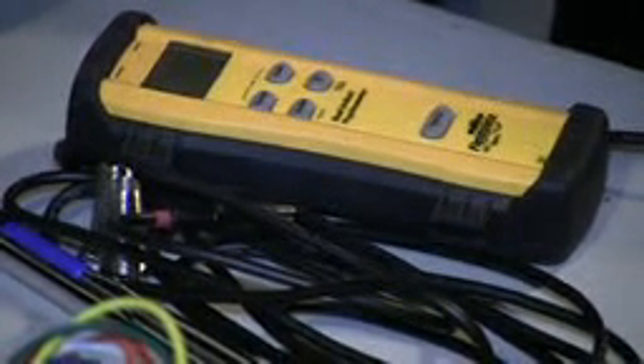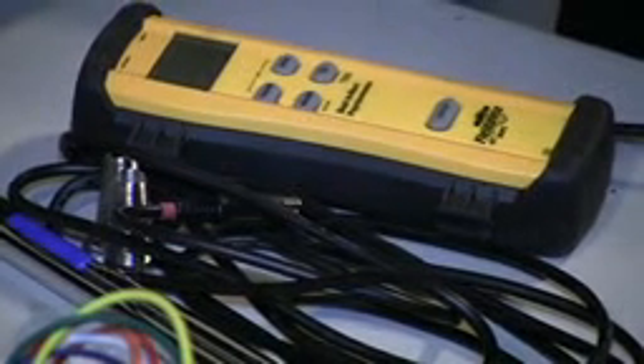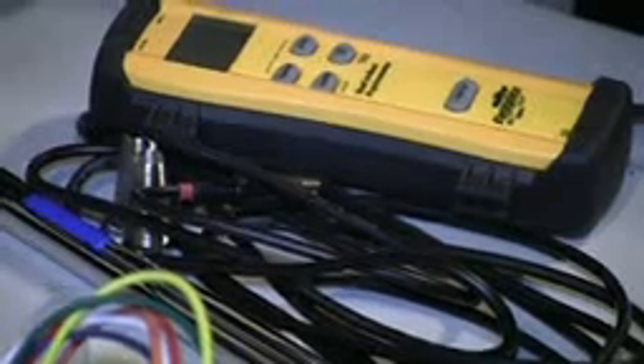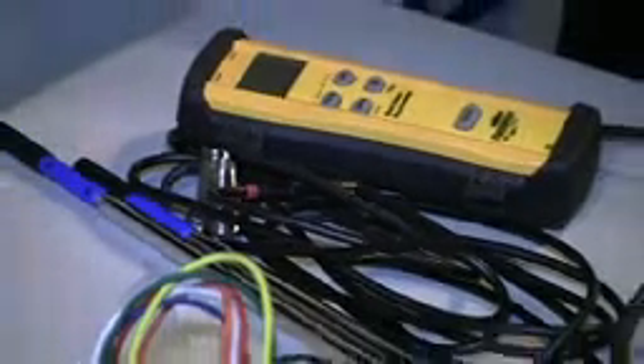Last but not least is my SDP2, my dual induct psychrometer. It allows me to check wet bulb, dry bulb, and dew point in both the supply and return, and helps calculate the BTUs for you. It's also a wireless device, so if you're doing superheat, you can sync it with your S-Man 4 to give it the indoor wet bulb temperature and help calculate your required superheat.